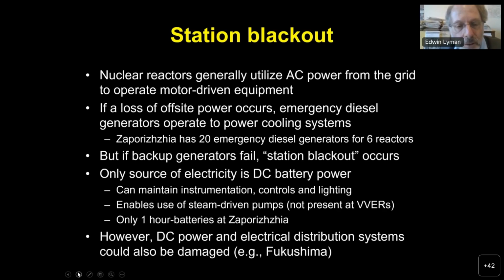In contrast to the US, where the NRC only requires 2 independent emergency diesel generators per reactor, Zaporizhzhia actually has 3, in addition to 2 additional generators that can be used for different units. So there are a total of 20 emergency diesel generators on the site for 6 reactors, and only 1 is really needed to maintain shutdown cooling for any of the reactors. So they have a lot of resiliency there.